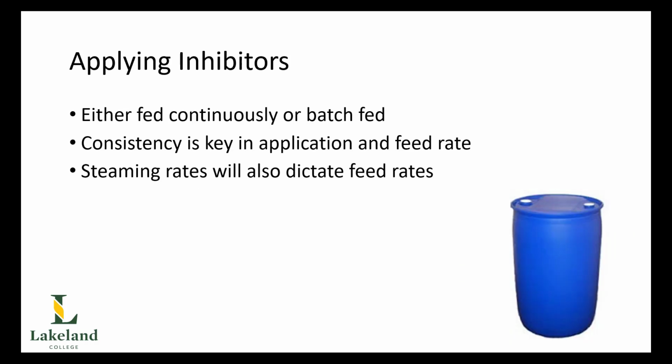Okay, in terms of applying the inhibitors, the inhibitors are either going to be continuously fed or batch fed, depending upon the application process and the chemical that's being used. Either way it's being done, consistency is the key in both application and injection rate, as this is what's going to minimize corrosion to an absolute minimum.